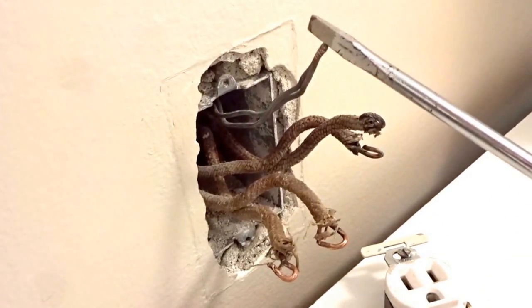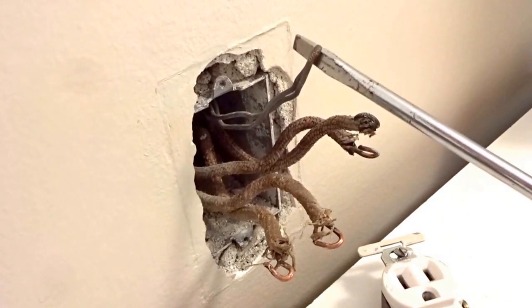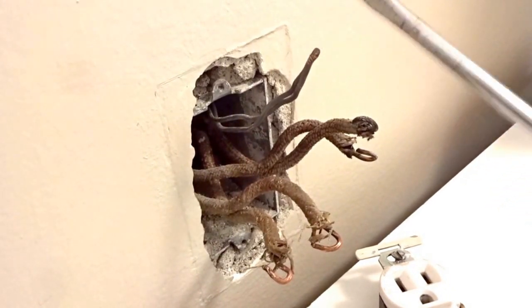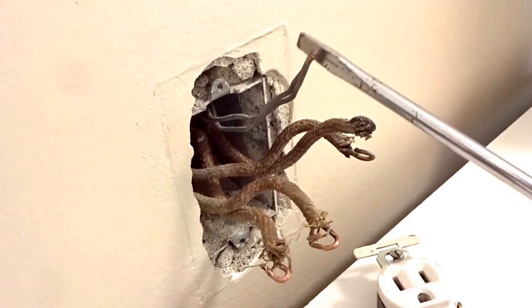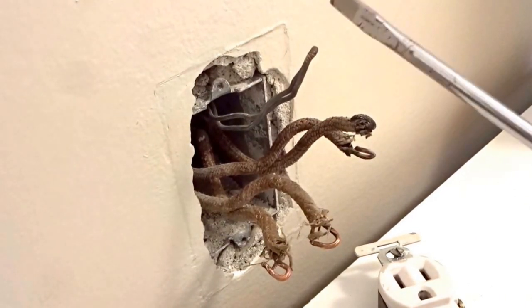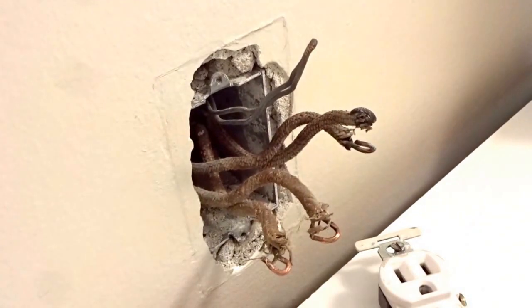And how often do you see this kind of mistake, Dylan? We see it a few times on the jobs you and I have worked on together. The thing about this is you would never know, because the lights will still come on and the power still works. But by having parallel paths to ground, you're creating a magnetic field because the current gets separated.